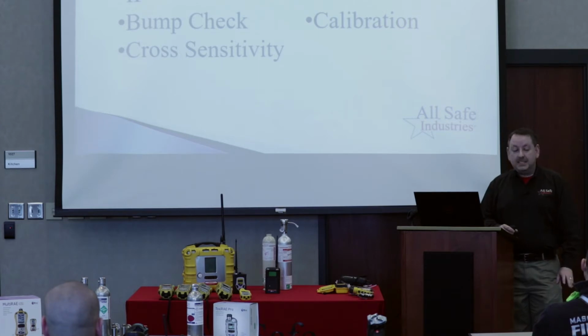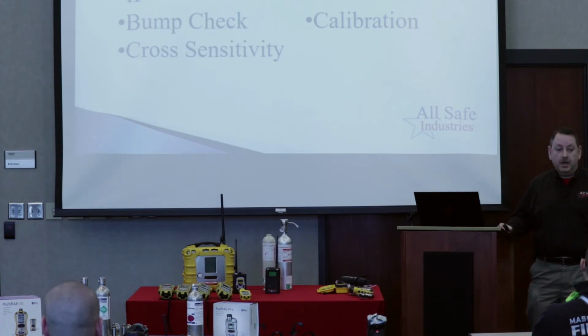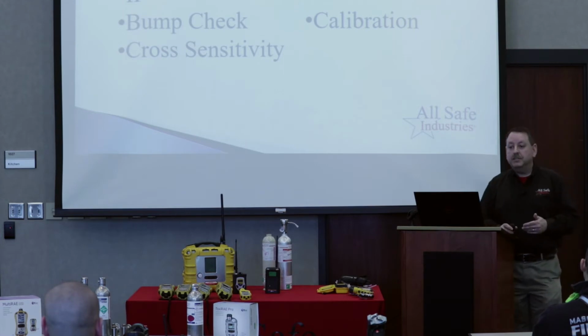Okay? And that's different than a calibration. A calibration is where we're actually going into the menus, we're telling the instrument, hey, I'm about to calibrate you. You'll use the same cylinder of calibration gas, but this time the instrument will let you adjust the readings so that they're more accurate. So I kind of refer to a calibration as an accuracy adjustment, okay? Because that's all we're doing. We're getting into the menus, we're feeding it a known value of gas from the cylinder, and we're saying, okay, reset yourself to these numbers.